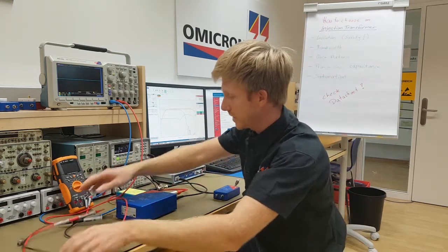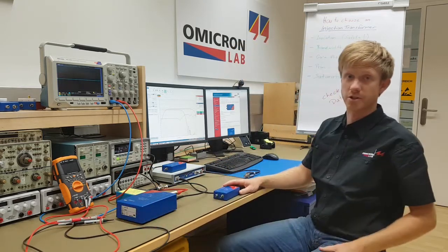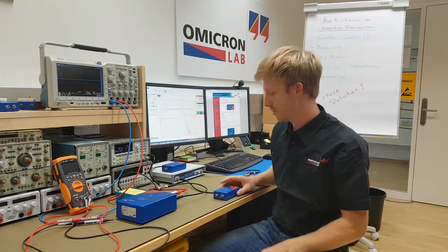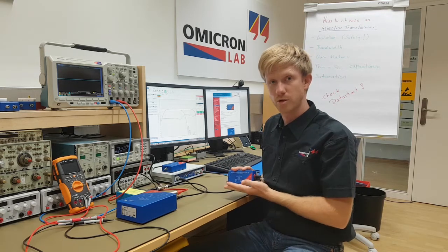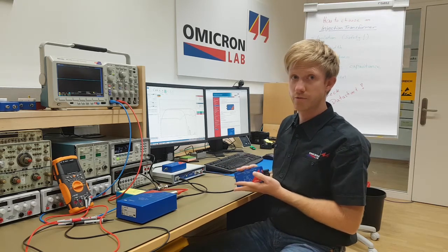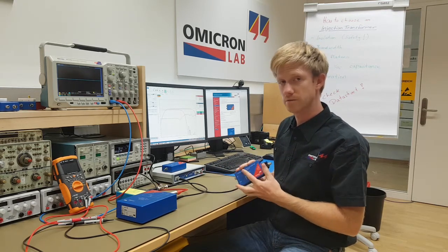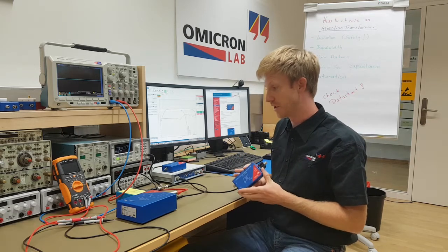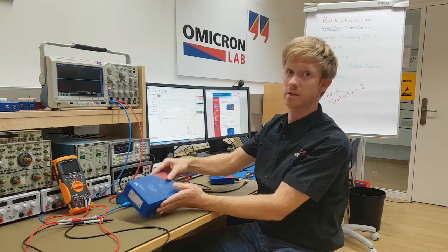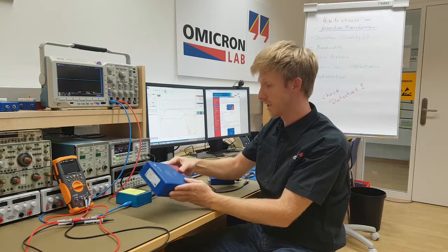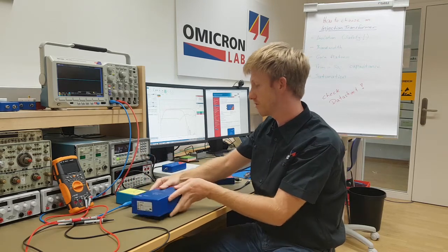The last point, last but not least, is saturation. As I already said before, the B-WIT 100 is quite small and tiny. It performs very well at high frequencies, but at 1 Hz you won't drive a lot of power with the B-WIT 100. For that you need a bigger and heavier injector. That's a really big and heavy one, our low frequency injection transformer.